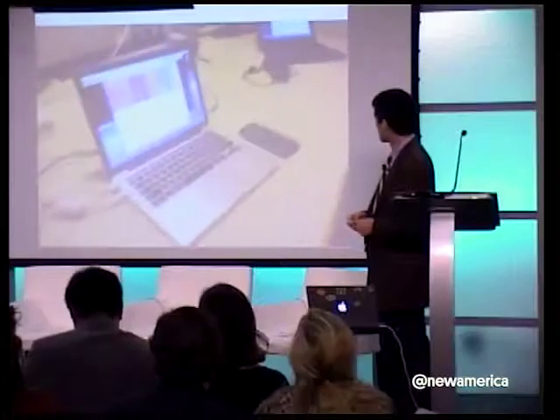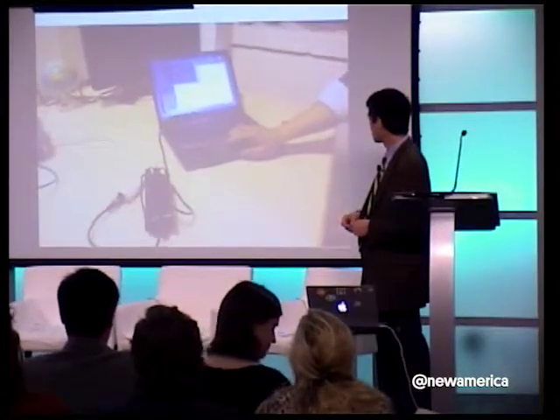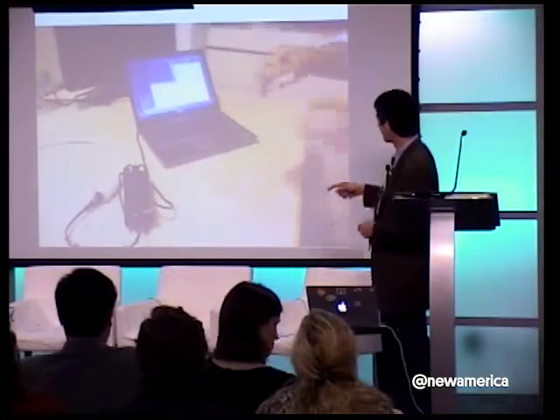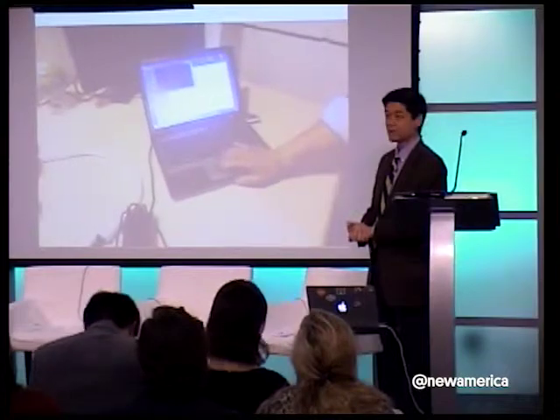We're going to do that using what's been reported to the FDA, and that is typically a vendor sticking a USB drive in, or a clinician who's copying electronic medical records, because don't forget, you keep things offline to keep them secure, and you sometimes use a USB drive to transfer things. So what we've got here is a cleverly disguised USB drive. It's got a picture of an insect on top of it. And we're about to plug it in innocuously, just like any clinician does every day.